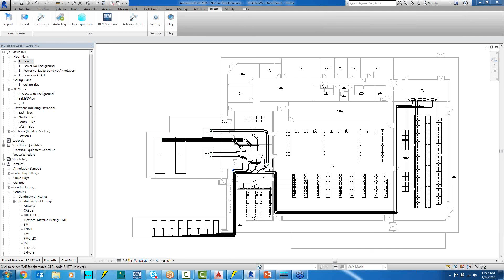Here's a layout. I've got my generators on the outside of the duct bank coming into my medium voltage switchgear, going back to my step-down transformer, feeding back into my low voltage switchgear, which then feed my motor control centers. Here are my air conditioning units on the outside, my UPS system with all of my battery banks here. I've got some conduits running over to the electrical room on the back side of the building, and then from there we're going to feed in cable tray under the raised floor to the racks in this room and to the racks in that room.